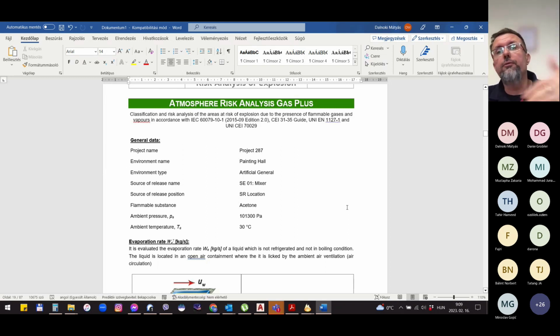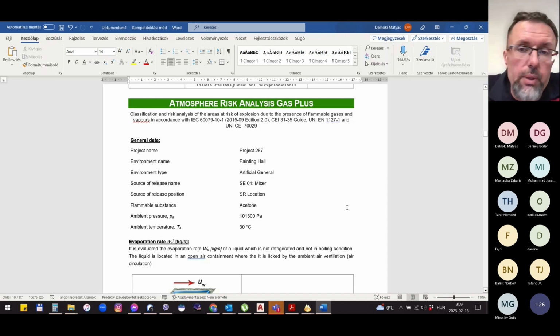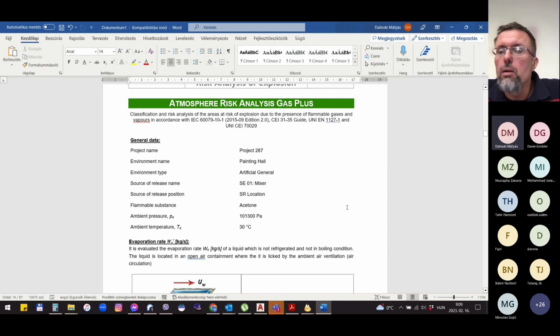So that's like a follow-up activity for any kind of project, okay? It doesn't matter if it's a service garage, a service station, or a refinery, or H2 technology. Yes, if you prepare explosion protection documentation, it shall contain ignition source analysis independently of the subject of the project.